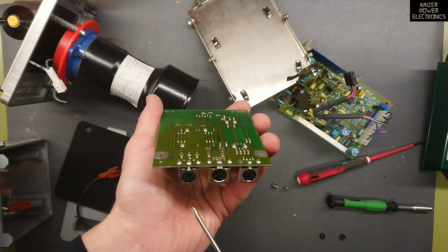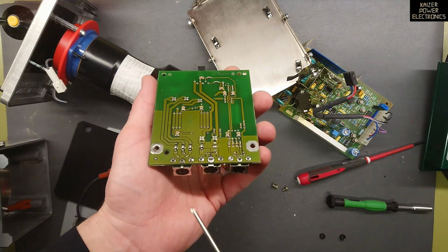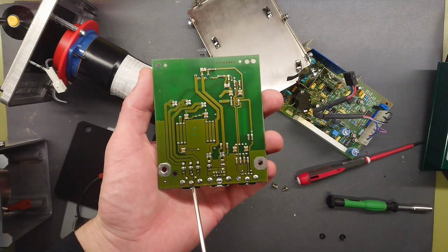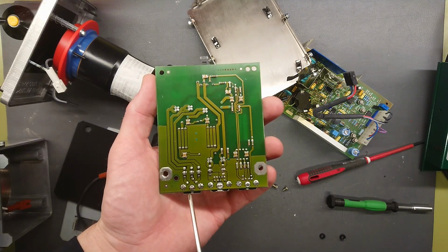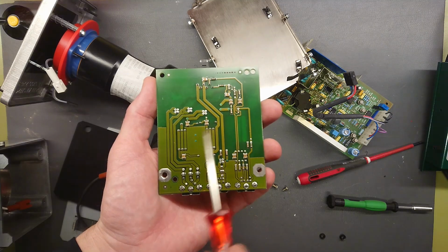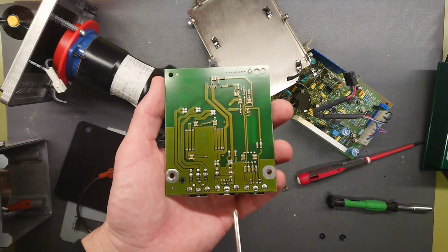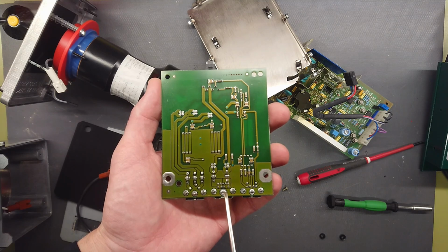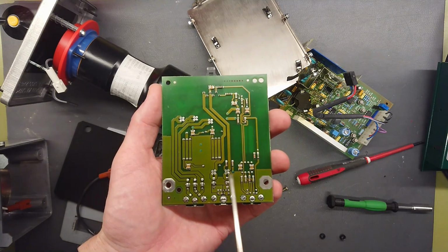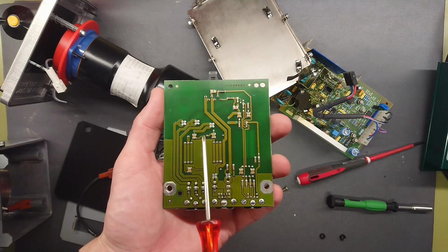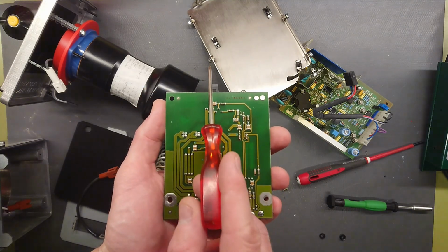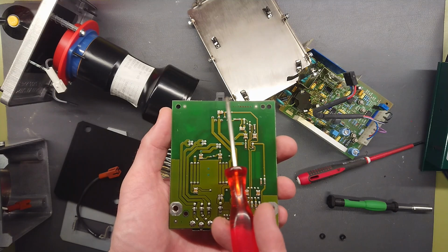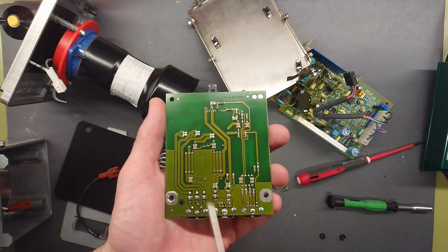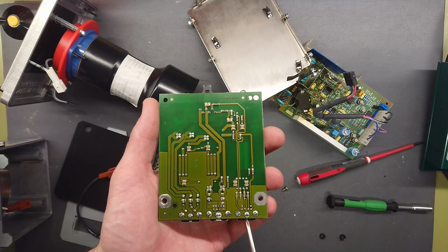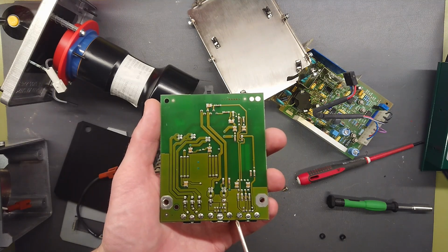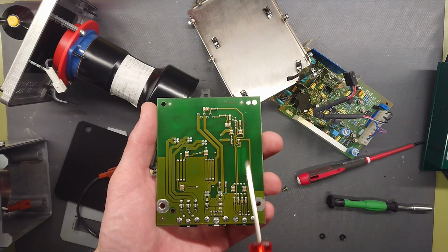On the back side of the connector board to the power supply, we can see that the 3-pin connector that goes to the PMT assembly is a plus minus 15 volt DC supply from this board to the PMT assembly. In the middle we have the 24 volt DC power supply, which just goes in here and goes directly up to the high voltage power supply, which then has the high voltage cable over to the PMT assembly. And over here we have the high voltage tension control, which goes through the two operational amplifiers.